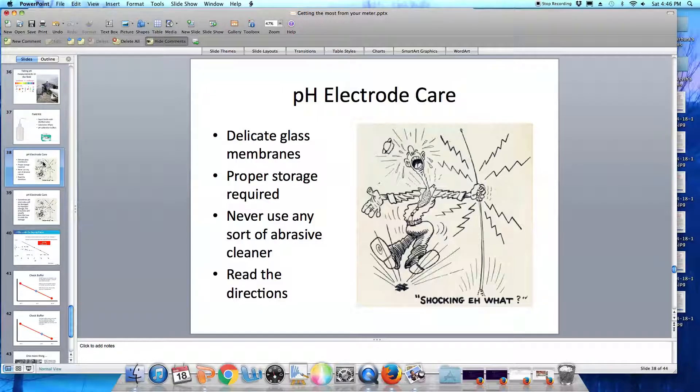You're never going to use any sort of abrasive cleaner on your pH electrode. And some people even say that you should never even rub it with a lint-free laboratory wipe, because that could build up an electrostatic charge on the electrode's surface.